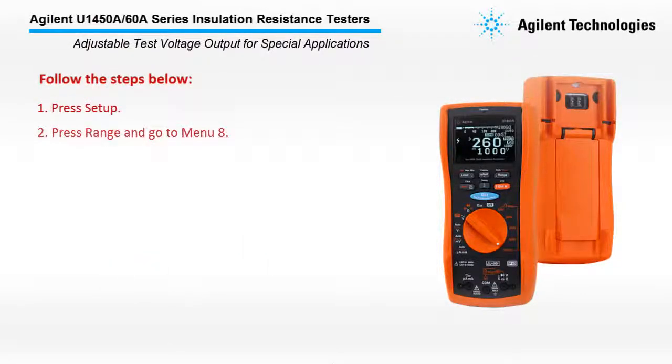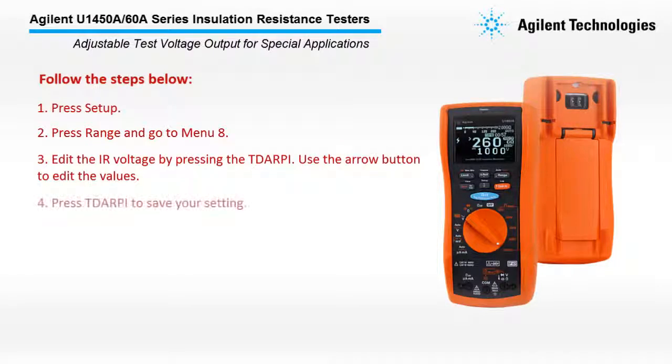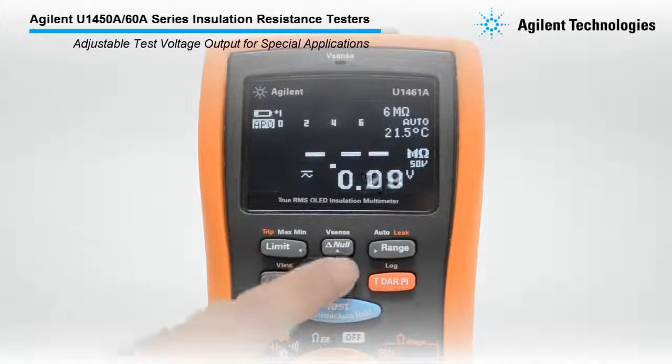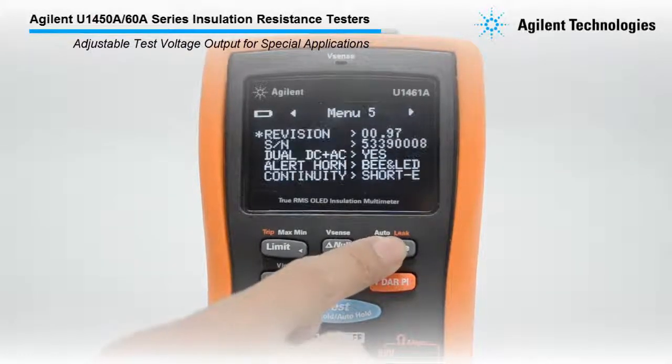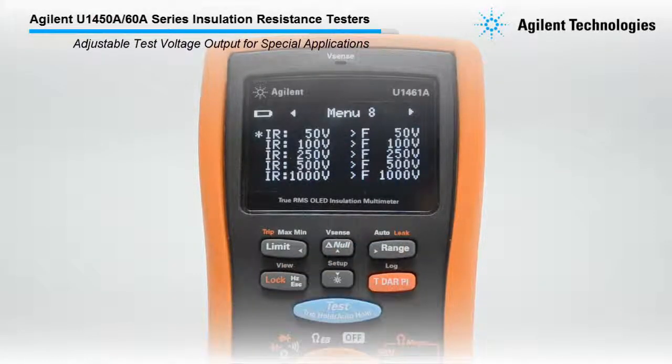The U1450A-60A Series allows you to adjust to your desired test voltage output from 10V to 1.1KV in 1V steps. Follow the steps below: press Setup, press Range and go to Menu 8, then edit the IR voltage by pressing the TDARPI button.